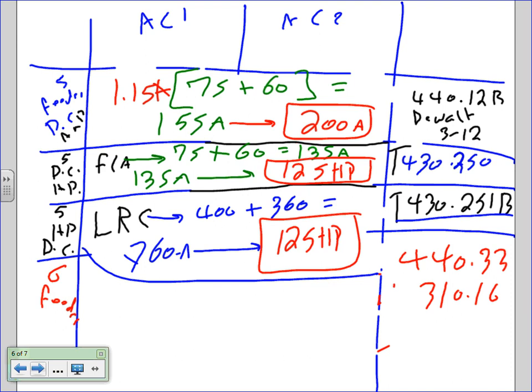How did you get from the 135 to 125? You have the full load current added up to 135 amps. Yep. And you go look that up under 430.250. Okay. Under the voltage 480. Yeah. Amp-wise, translate to horsepower. It's kind of a reverse function. Instead of having the horsepower and finding the full load current, now we're taking a full load amp and reversing it into the horsepower. Same thing, guys. We're used to having a horsepower and a voltage and finding the full load current. This is the opposite. I have a full load current and I need to find the horsepower. So if 135 is not a standard, what do you need to do? You have to go to the next one, right?